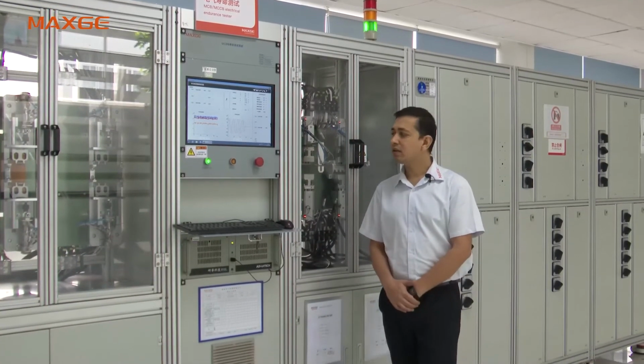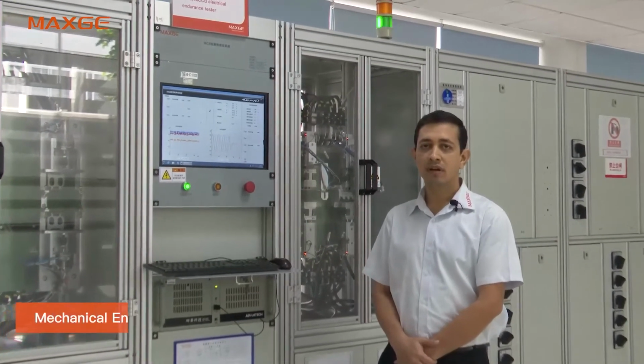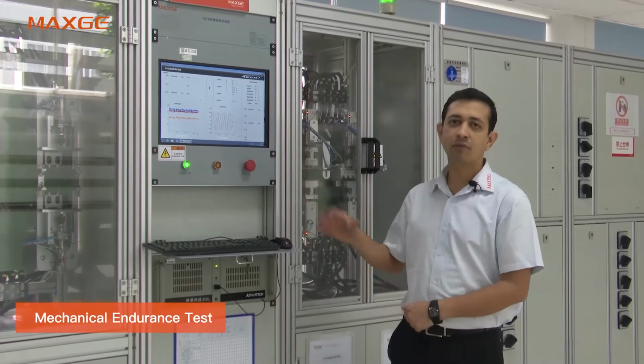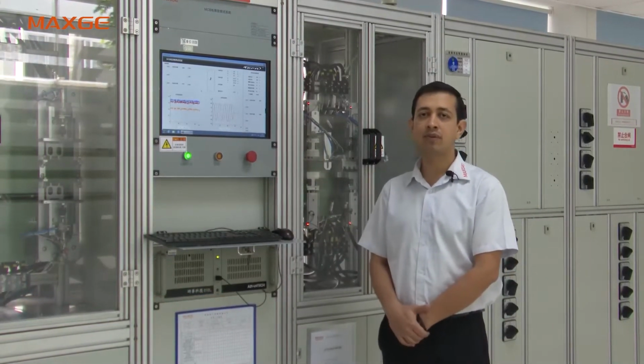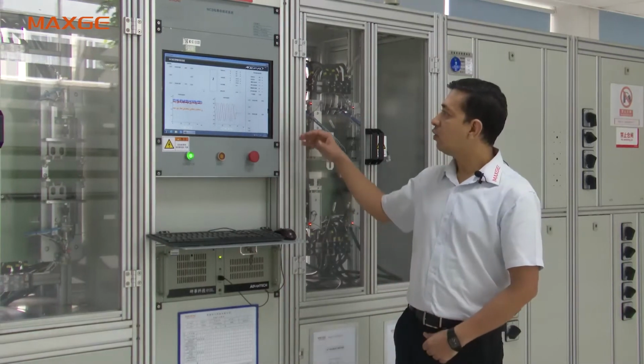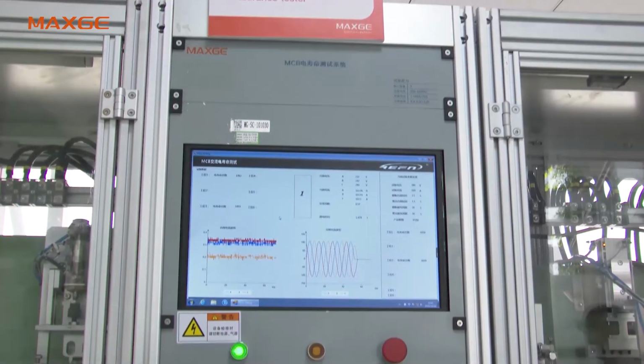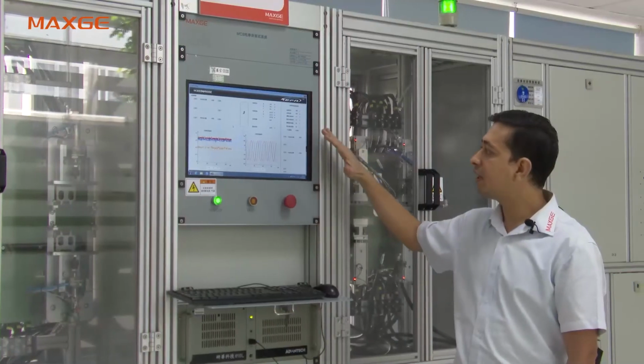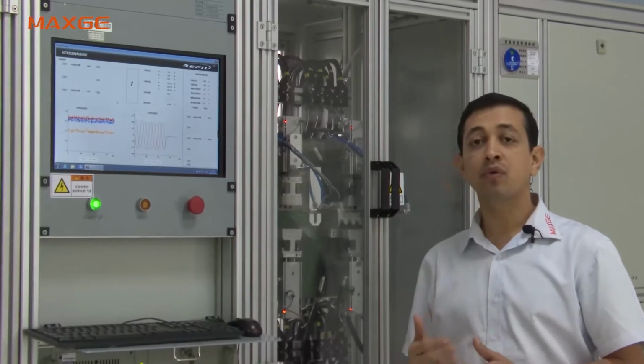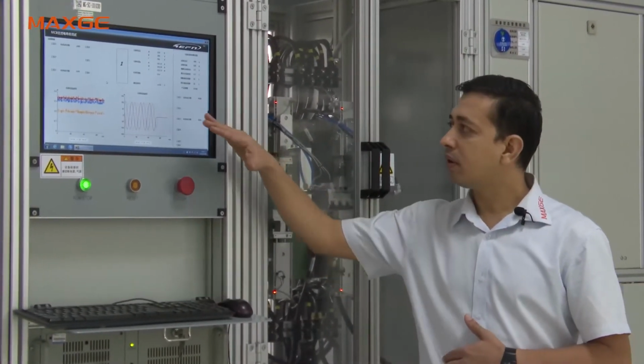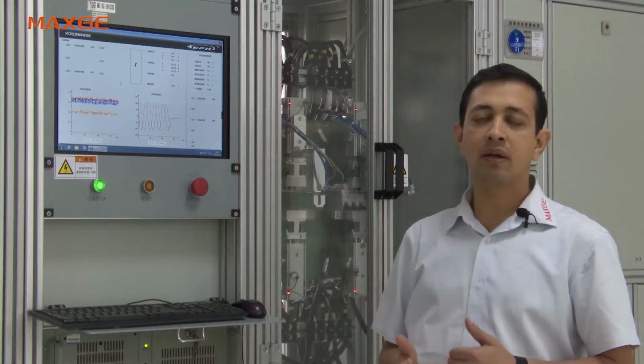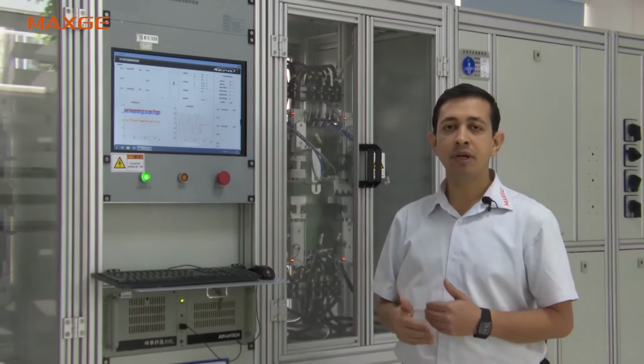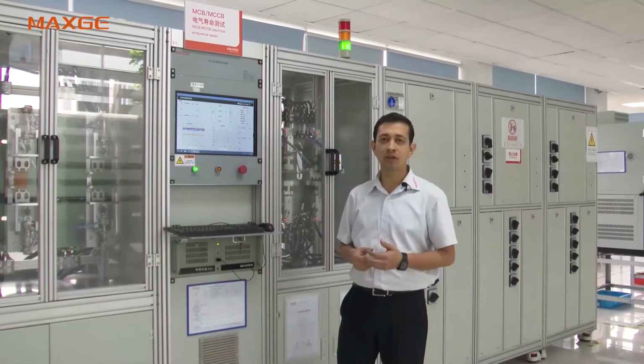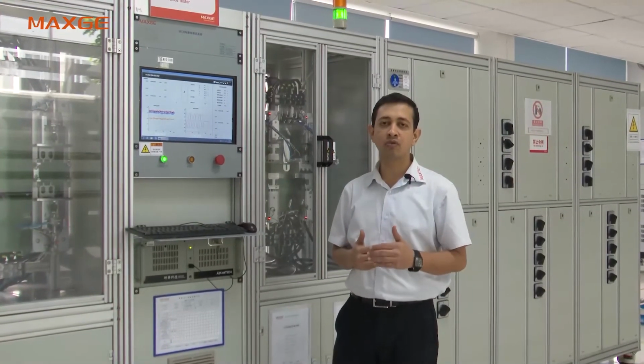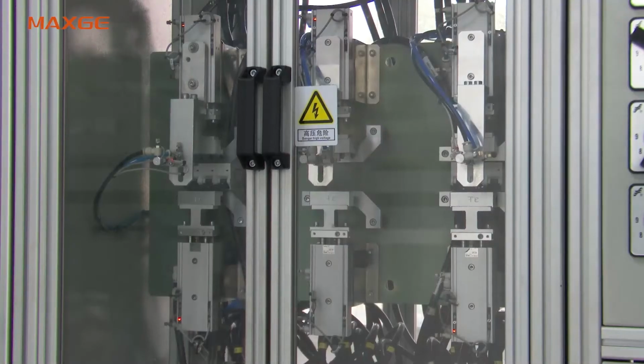Now we are standing at the electrical endurance test machine. This machine can test as per IEC 60898 standard and also IEC 60947 Part 2 standard. You can see on the screen the rated voltage and rated current are applied during the test, and the power factor is also maintained. This test lasts for several operations, and normally the MCB or MCCB will be turned off for 28 seconds and turned on for 2 seconds. Likewise, there are many operations it has to sustain as per standard. The limits are already mentioned in the standard.